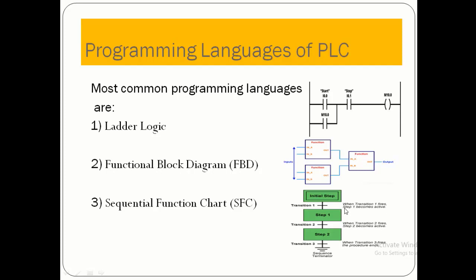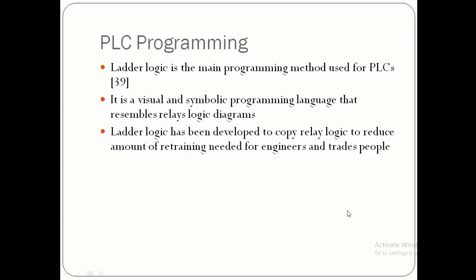In some modern PLCs we can convert ladder language into FBD or SFC as per requirement. Ladder logic is the main programming method used for PLCs — it is a visual and symbolic method that resembles relay logic diagrams. It was developed to copy relay logic to reduce retraining needed for engineers and tradespeople. It takes very less time — almost 16 milliseconds to convert an input to the output — and is the most widely used method for PLC programming.